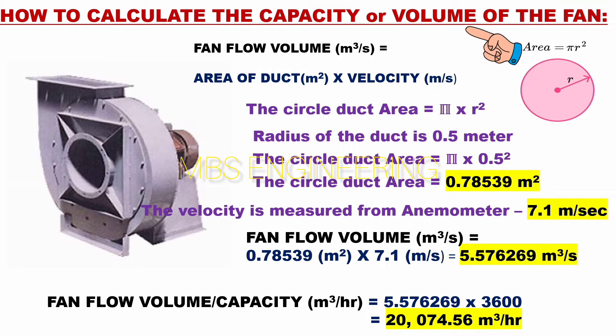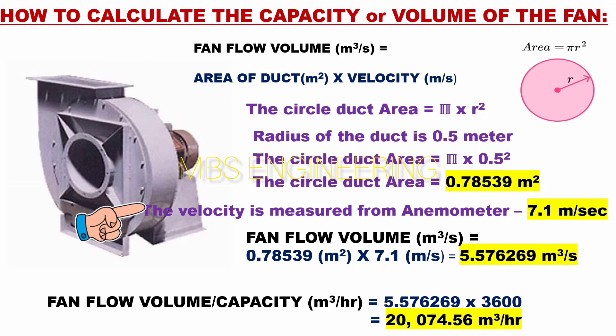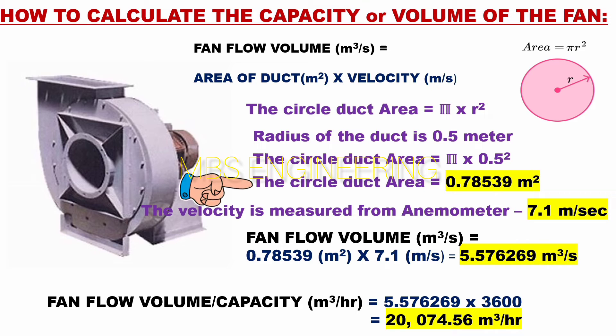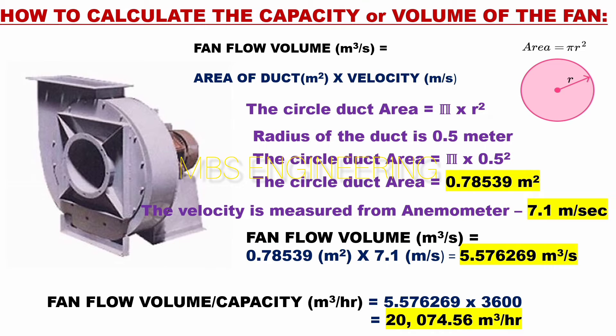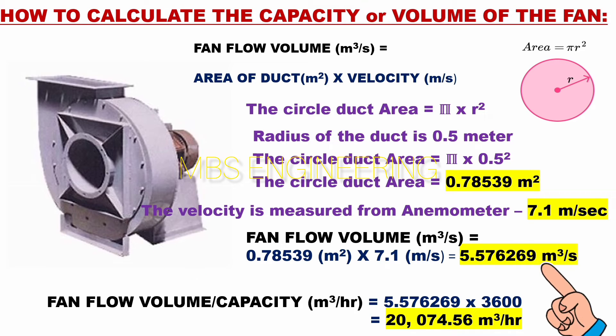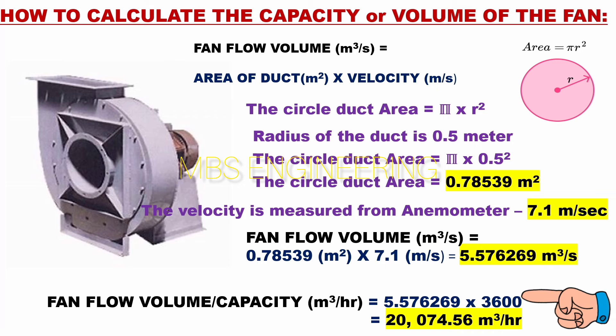The fan flow volume or capacity is equal to the velocity multiplied by the suction ducting area. The anemometer-obtained suction velocity is 7.1 meters per second, and the suction ducting area is 0.78539 square meters. Therefore, the fan flow volume is 0.78539 × 7.1 = 5.576269 cubic meters per second. Converting to cubic meters per hour: 5.576269 × 3600 = 20,074.56 cubic meters per hour.